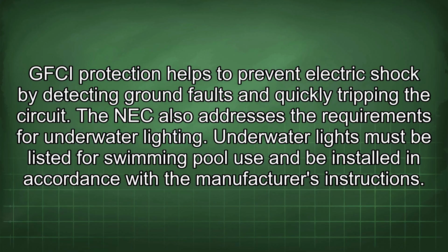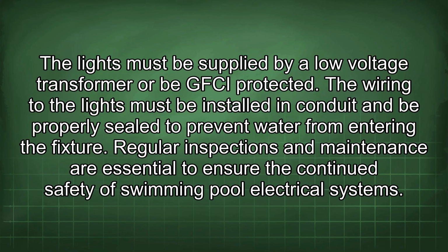The NEC also addresses the requirements for underwater lighting. Underwater lights must be listed for swimming pool use and be installed in accordance with the manufacturer's instructions. The lights must be supplied by a low-voltage transformer or be GFCI protected. The wiring to the lights must be installed in conduit and be properly sealed to prevent water from entering the fixture. Regular inspections and maintenance are essential to ensure the continued safety of swimming pool electrical systems.